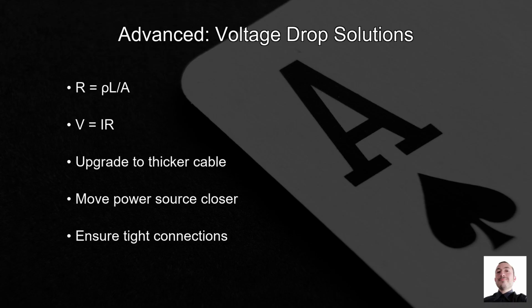Once you have the resistance, you can calculate the voltage drop using Ohm's law, V equals IR. If the voltage drop is significant, consider upgrading to a thicker cable with lower resistance. Another solution is to move the power source closer to the load, reducing the cable length. Additionally, ensure all connections are tight and free of corrosion to minimize additional resistance. For more precise control, you might consider using a voltage regulator or a transformer to stabilize the output voltage. Remember, the goal is to maintain a consistent voltage at the load to ensure optimal performance.